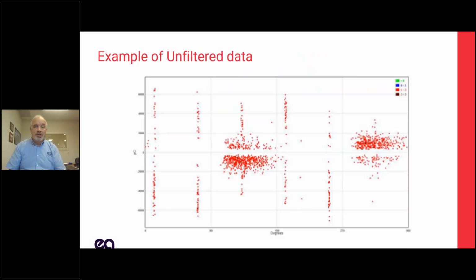Very often, you'll get both in the same plot. Here I've got the vertical spikes of a VFD, but I've got those 2 clouds half a cycle apart, positive and negative, showing me that I've got something else. So if I look at the peak levels, well, the peak levels are coming from that VFD. That will be very misleading.